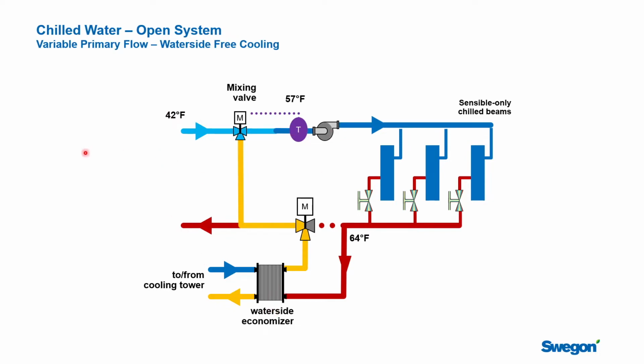You need to do a little bit of thinking about what temperature you're going to ask the cooling towers to operate at. When you're in economizer mode, that water's got to be colder than 57 degrees. If you have a 2-degree approach on your heat exchanger, that means you've got to pull this water down to at least 55 degrees, which is pretty cold for chillers. So you would need to think about it if you're running the tower plant to make 55-degree water for free cooling, but you want to run some mechanical cooling. You'll need to slow down and think about how you're going to make that water a little bit warmer for the chillers themselves. 55-degree water would be pretty cold. Check with your chiller manufacturer.